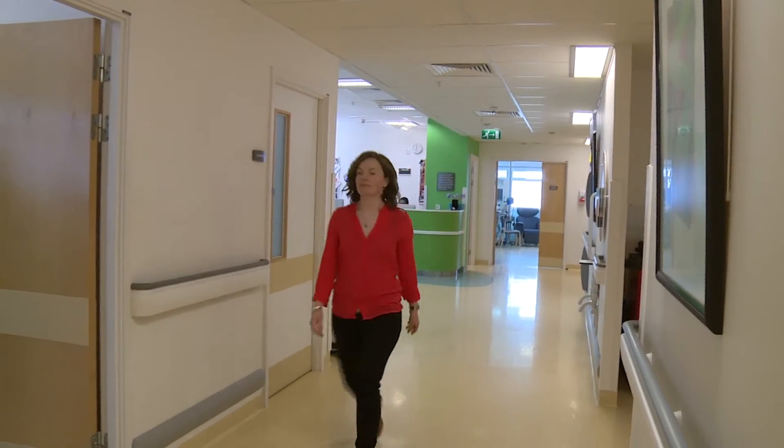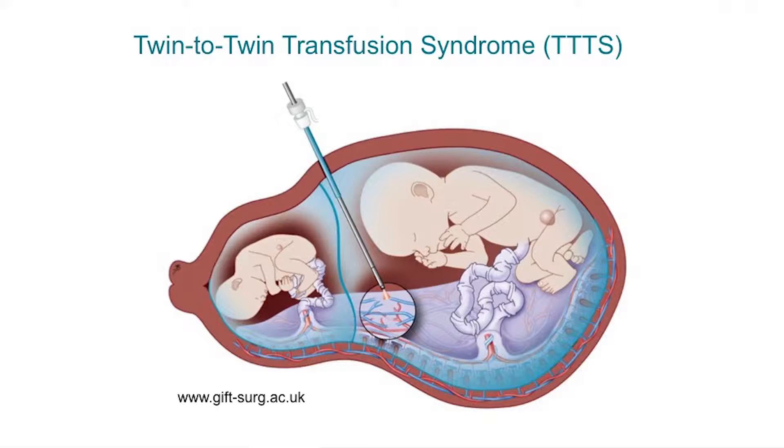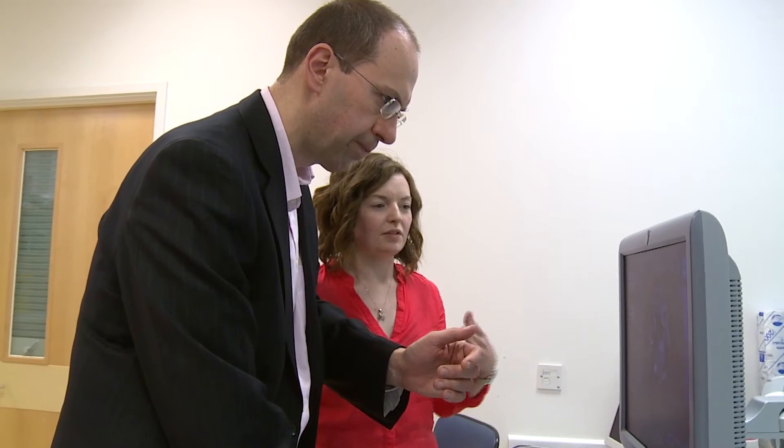I'm Ellie Martin. I work in the biomedical ultrasound group in the medical physics and bioengineering department at UCL. In this project we aim to develop a fiber optic sensor with a Fabry-Pérot etalon detector at the end for sensing the ultrasound. These type of sensors have much higher sensitivity and lower noise thresholds than traditional piezoelectric ultrasound sensors, so are well suited to this kind of application.